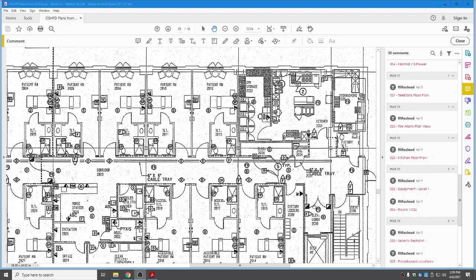Jump down here, you can see on the lower right these two half shaded boxes here are showing these egress doors here are held open with a mag hold open device with a speaker and a D, which would be our smoke detector. Over here near the stairway exit, you can see a manual pull station with a visual 15 candela strobe device and a fire alarm speaker.